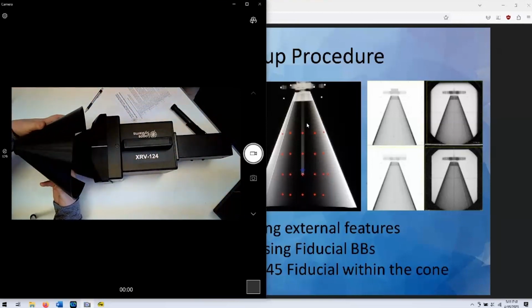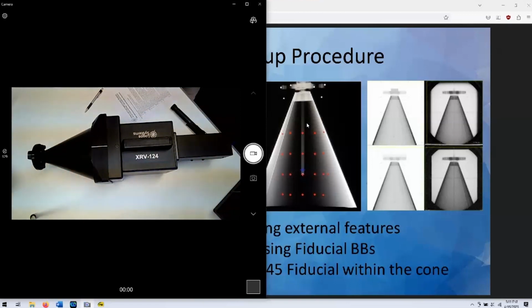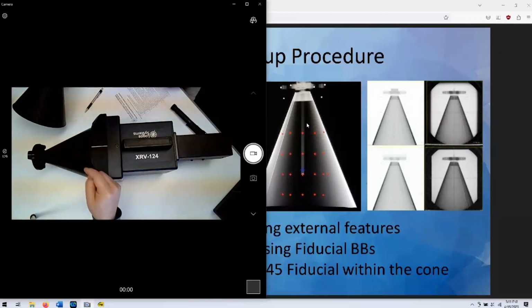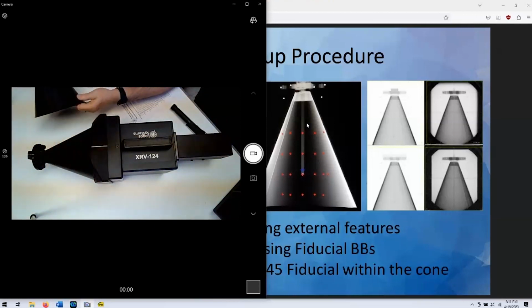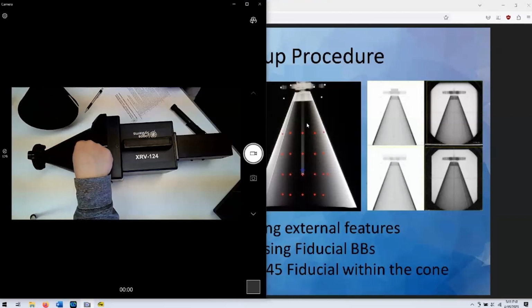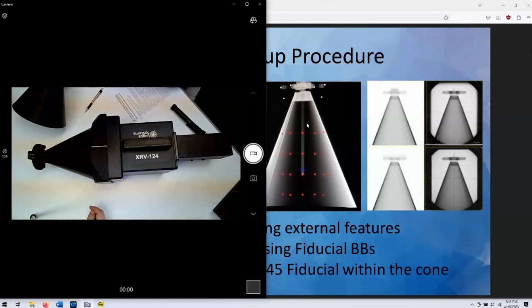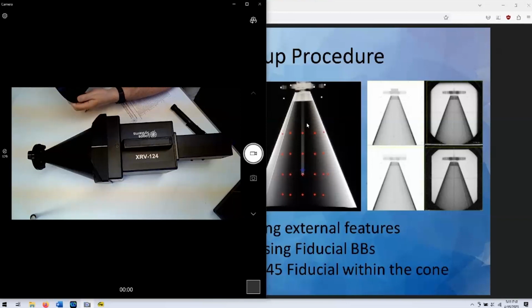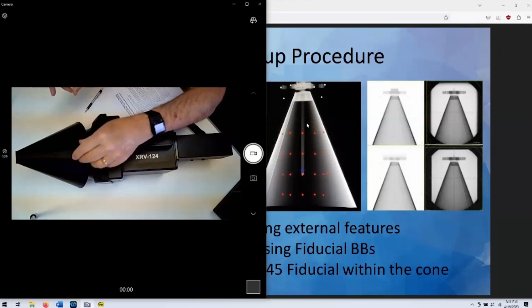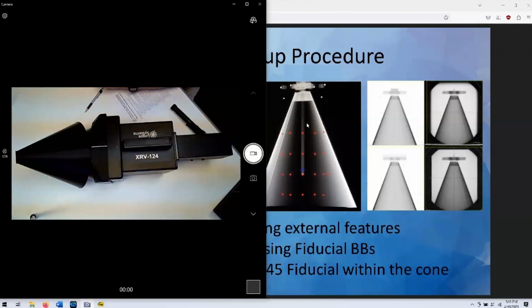Using the XRV-124 without the shroud is useful if laser alignment is somehow part of the chosen measurement procedure. The treatment room lasers and lights should be turned off if the XRV-124 is being used without the shroud. The shroud will need to be removed during the calibration procedure. A hybrid approach to removing the shroud would be to remove only the tape and keep the shroud attached. The shroud can then be rotated around the imaging cone to expose only reference holes north, east, south, or west, needed for the laser alignment.